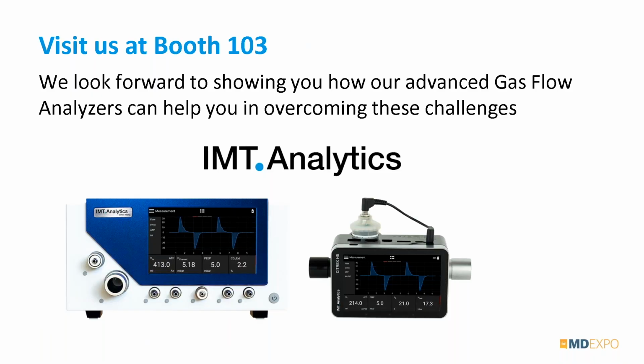And I can't tell you how many times I've said, did you do the zero calibration? And people go, well, we send it in for calibration once a year. It's like, no, that's the user calibration. Yes, a lot of analyzers say send it in for actual calibration, but there are calibrations that you need to do each time before you use it. Same way with it, it might have an oxygen cell. It's important that you calibrate that oxygen cell as well.